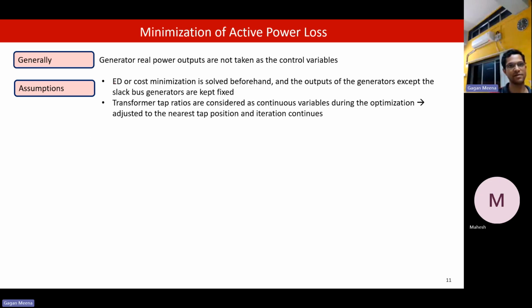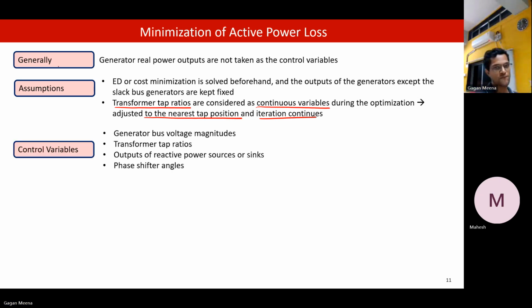Here we do this economic dispatch or cost minimization. We solve it beforehand and the outputs of the generators except the generator at the slack bus are fixed. And then the transformer tap ratios are optimized to minimize the total loss. These are considered as continuous variables and then they are adjusted to the nearest tap position in each iteration. And these are the different control variables used in minimizing active power loss problems. One is the generator bus voltage magnitude, then transformer tap ratios, output of reactive power sources or sinks, and the phase shifter angles and all.